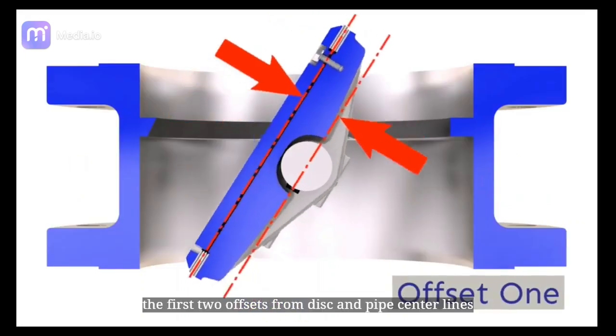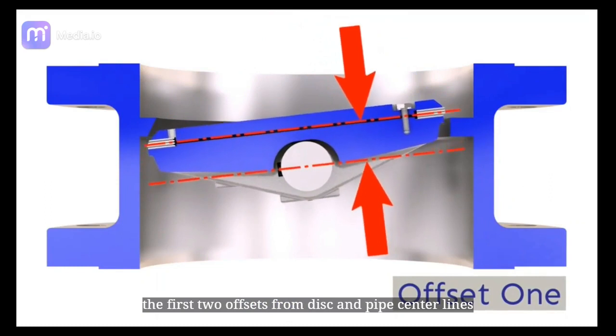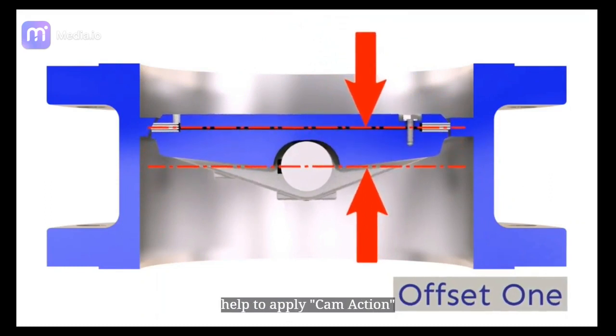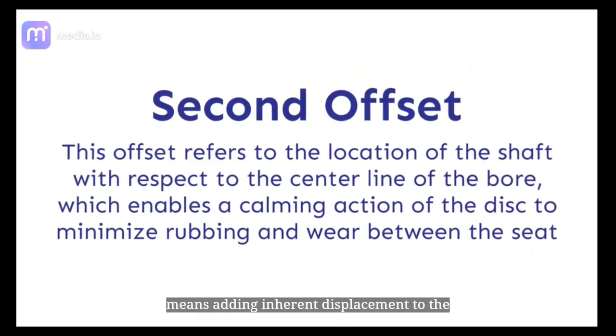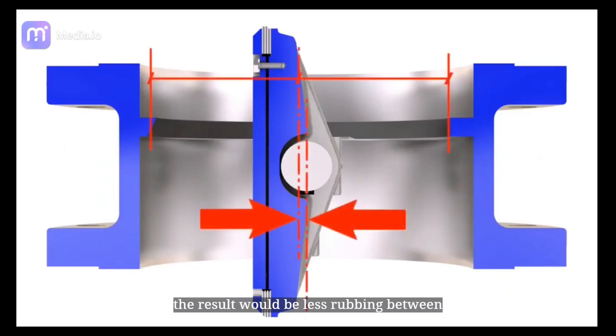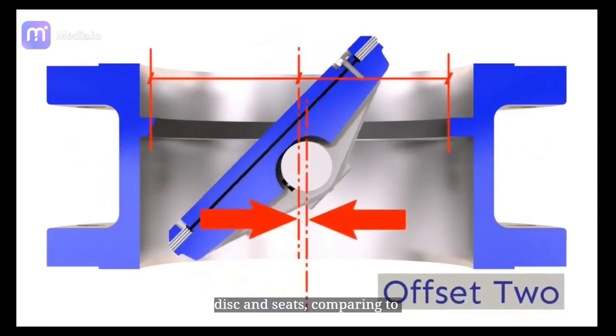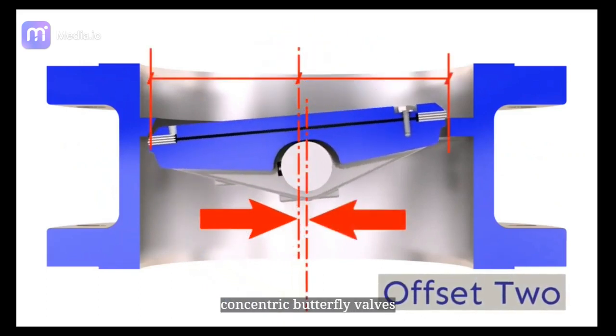The first two offsets from disc and pipe center lines help to apply camming action, meaning adding inherent displacement to the rotational motion. The result would be less rubbing between disc and seats comparing to concentric butterfly valves.